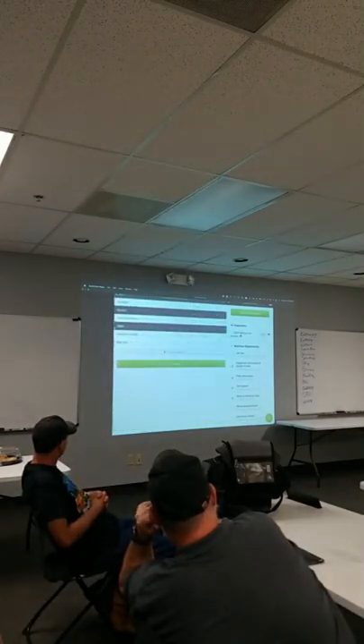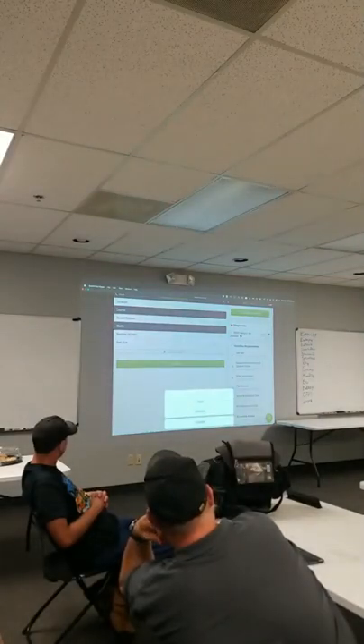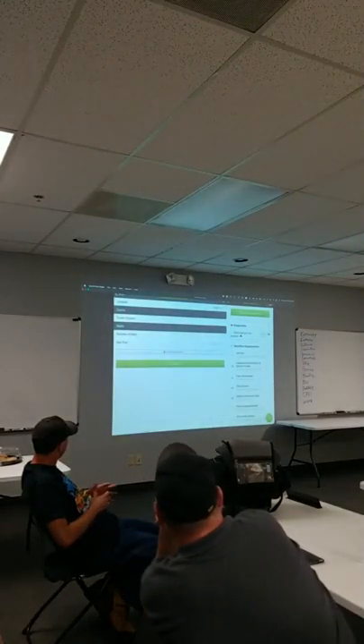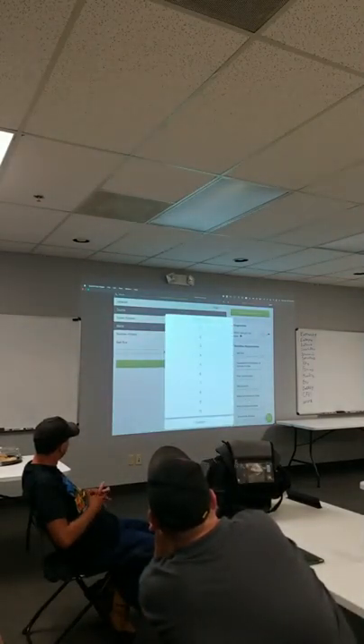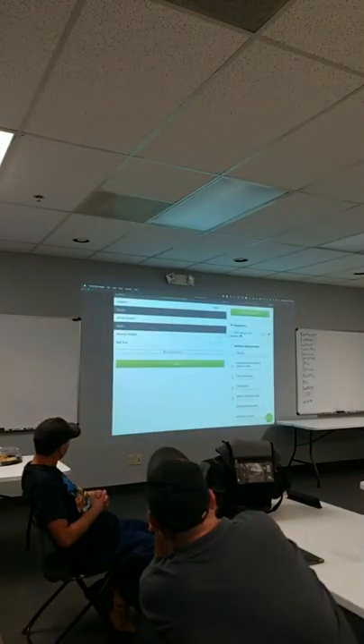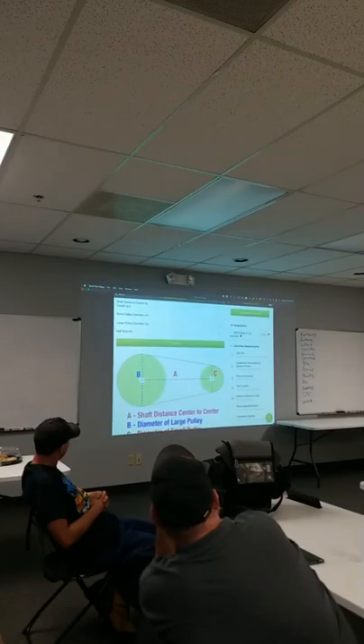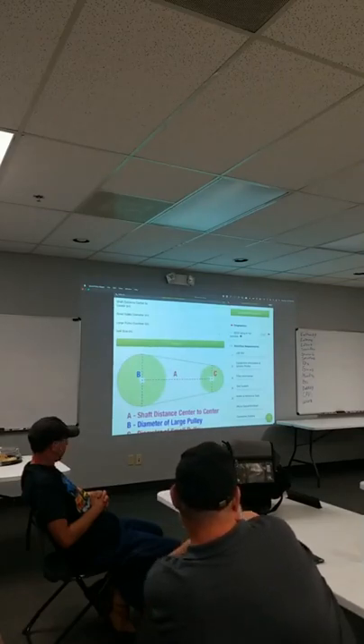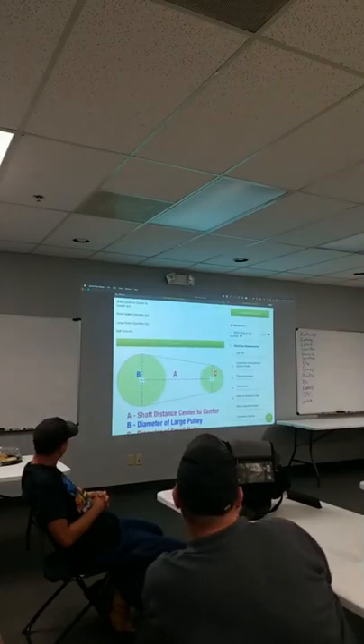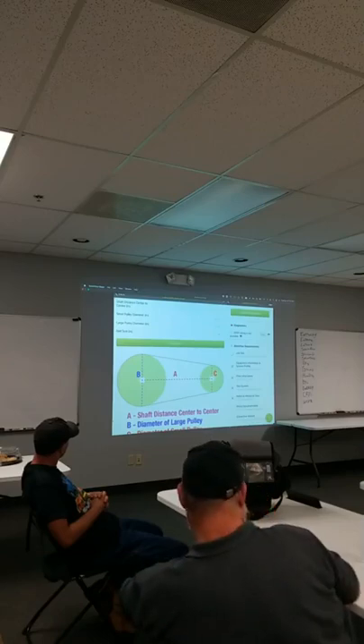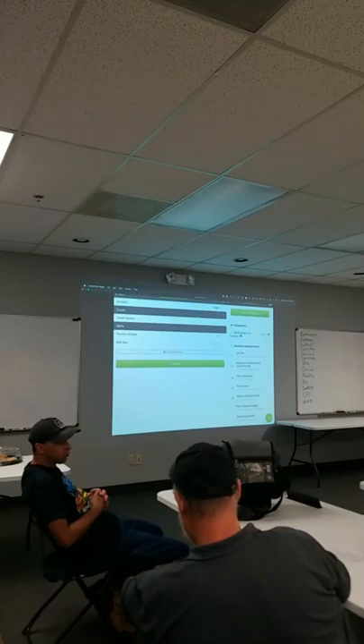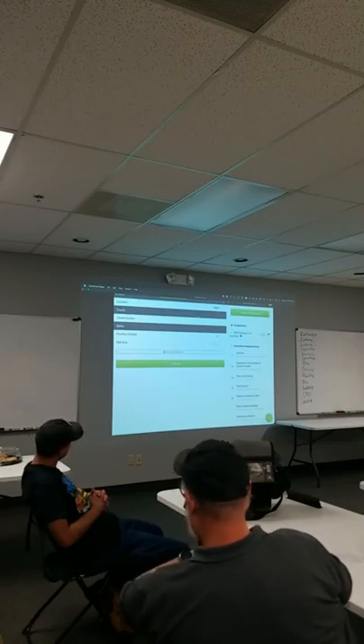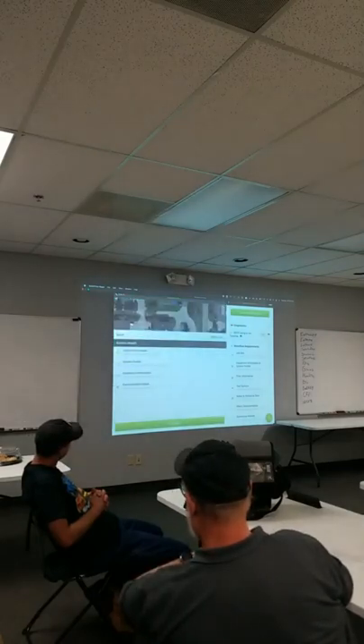Installation information, this is just location, is it on a roof or is it on the ground, is it zoned or not, does it have any belts on there? So if it has a belt size on there, you can say if it's got 1 or 2 belts. We also have a little calculator here. If you want to calculate your belt size, if the belt's broken, you can put in your shaft distance, your small pulley diameter, large pulley diameter. It'll calculate the belt size. Is that pitch diameter or OD? It's OD. And then you hit continue on there.